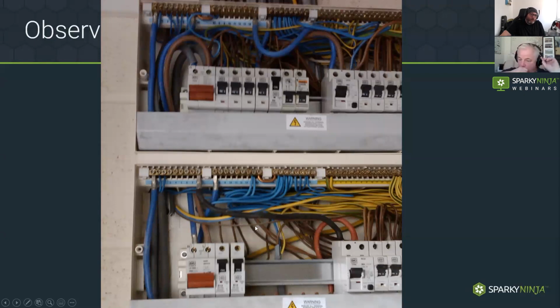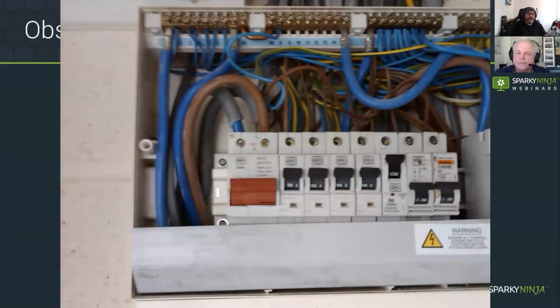This board will all go off, but the live conductors will all still be energized. Yeah. We don't single pole switch neutrals, and that's what this situation has done. Yeah, there, with that little thing. This live coming out there, but the neutral comes out of the bar here, which is actually through this isolator.